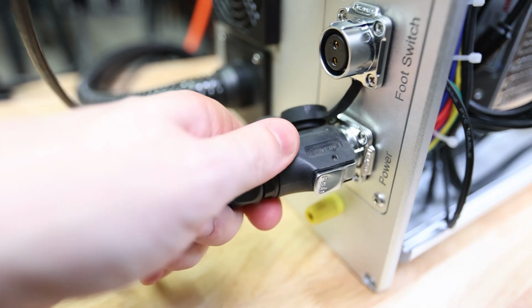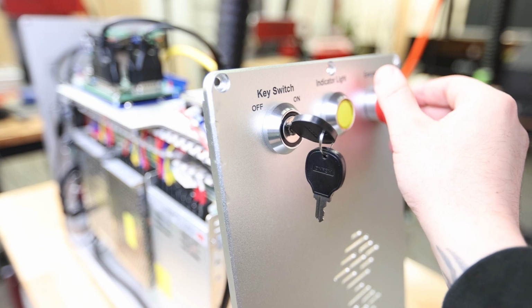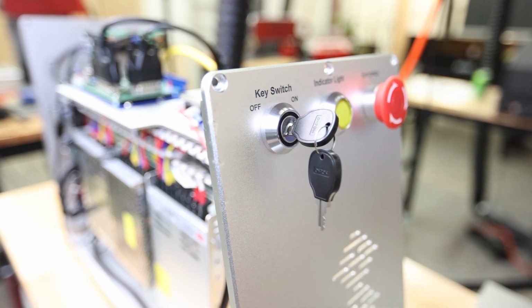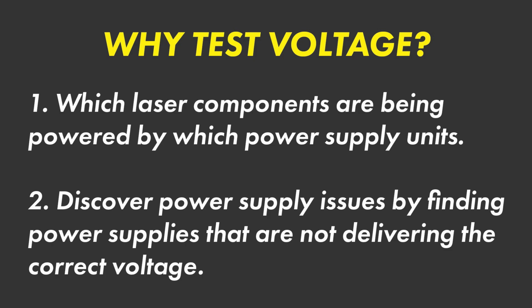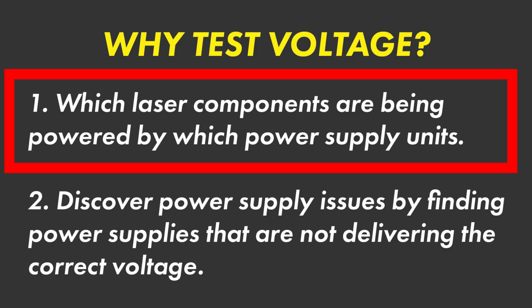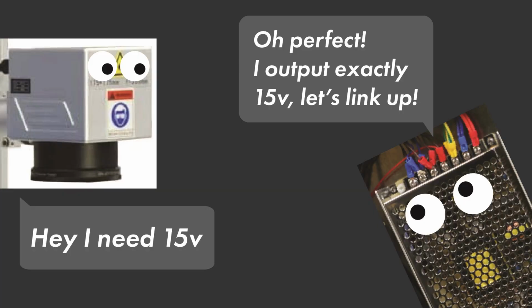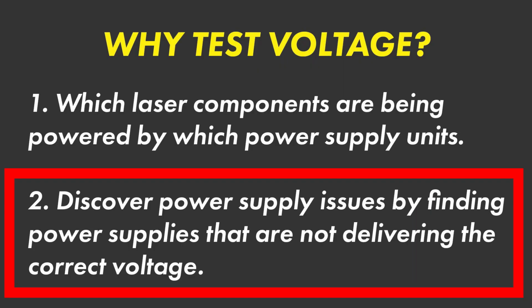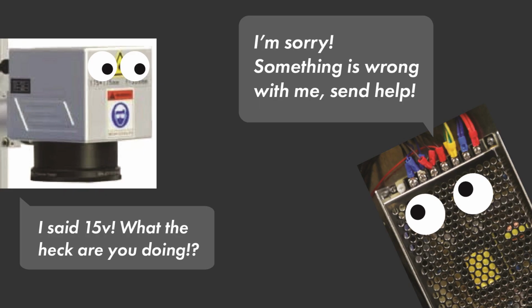With our continuity tests complete, you may now plug your machine back into the wall. Exercise extreme caution from here on out, as there are likely multiple points inside your machine which will deliver an electric shock if you touch them while energized. Testing the voltage being demanded by our power supplies will tell us two very important things. First, we will be able to determine which laser components are being powered by which power supply. We can achieve this by matching voltage demand from the component with the voltage supply from the PSU. Second, we will be able to diagnose issues with our power supply if we determine they are not supplying the power for which they are rated and for which the components require to operate properly.